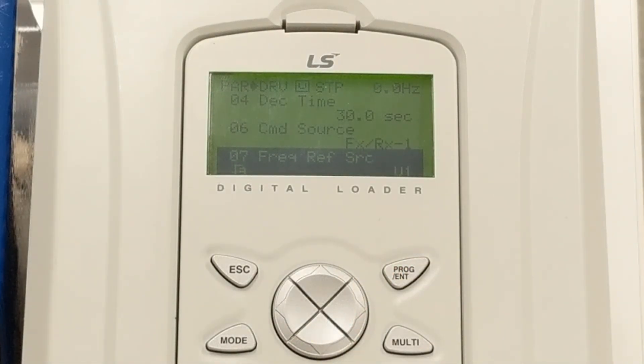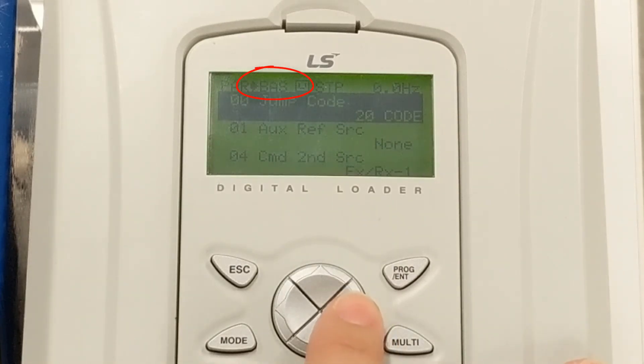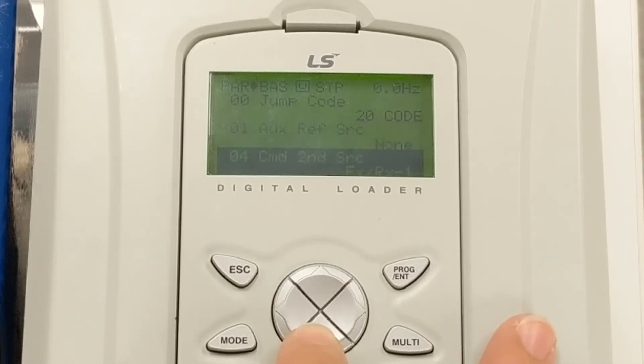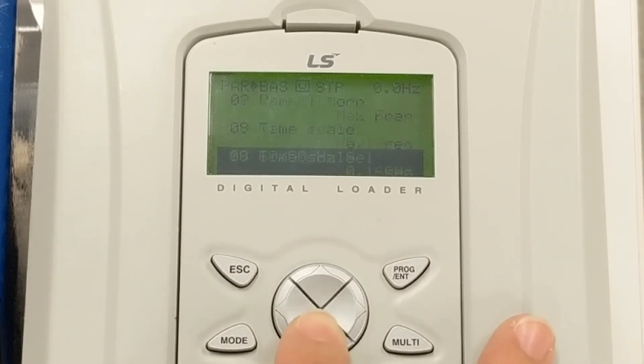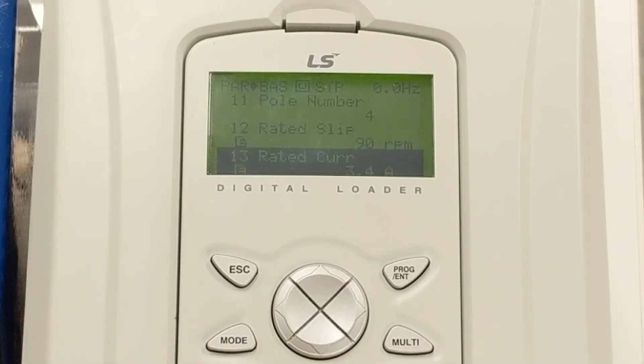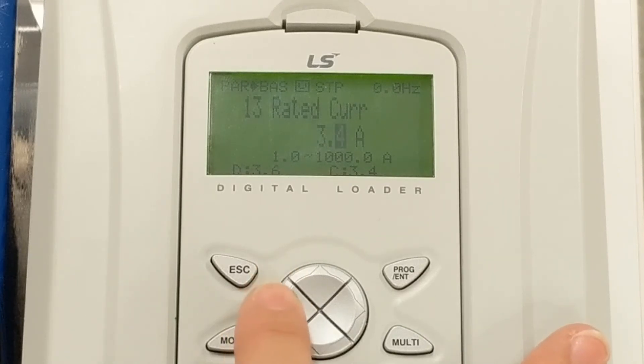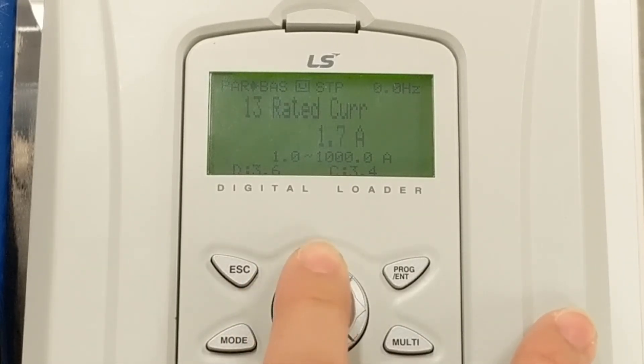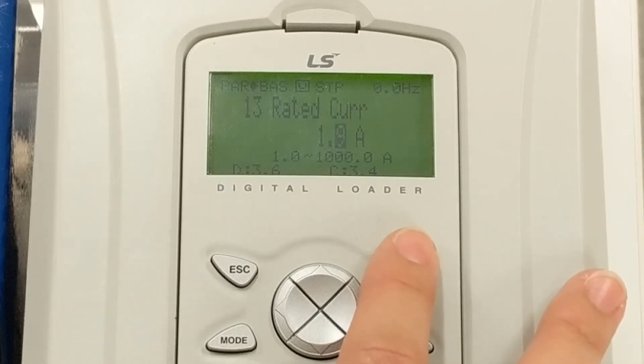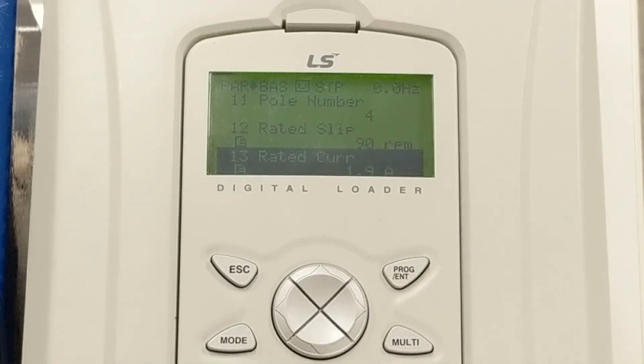While we are in programming, let's check another important parameter. Press the right arrow to navigate to the BAS group. BAS stands for basic parameters. Press the down arrow until you get to parameter 13, rated current. This is where you need to set the motor's full load amps based on the motor nameplate data. Our motor here is 1.9 amps at 230 volts. Press the program enter key and use the arrows to adjust the setting to your motor FLA, then press the enter key once again once you have set it. This setting is important as it sets the overload level to protect your application and the motor itself.